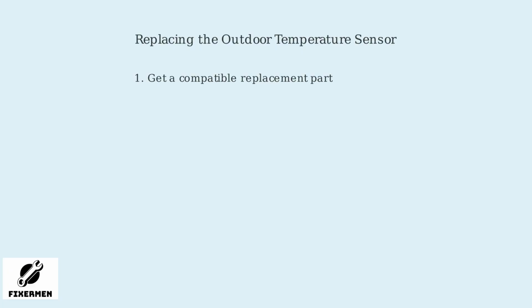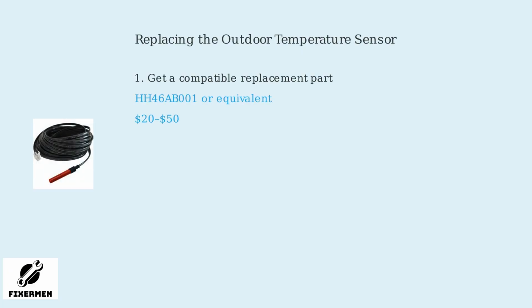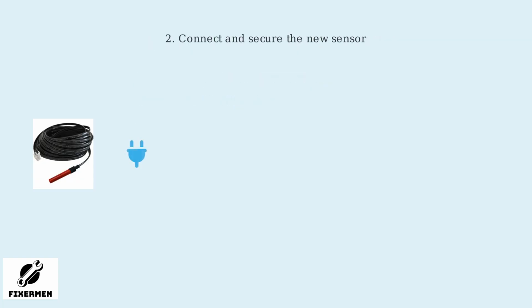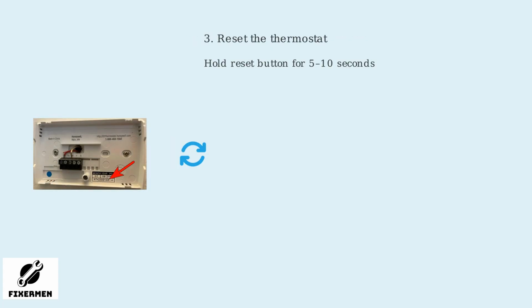If the sensor is faulty, replace it with a compatible part like HH46AB001 or equivalent, which typically costs $20 to $50. Ensure the new sensor is properly connected and secured to the outdoor unit. After replacing the sensor, reset the thermostat by holding the reset button for 5 to 10 seconds. This clears the error code and allows the system to recognize the new sensor.